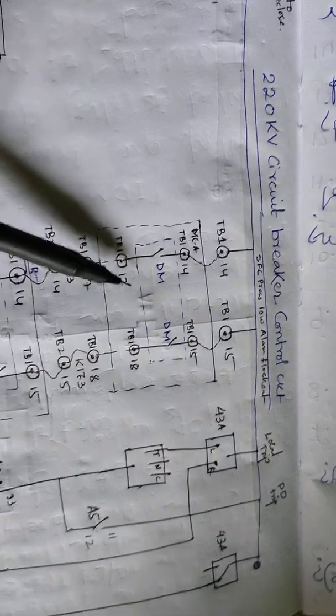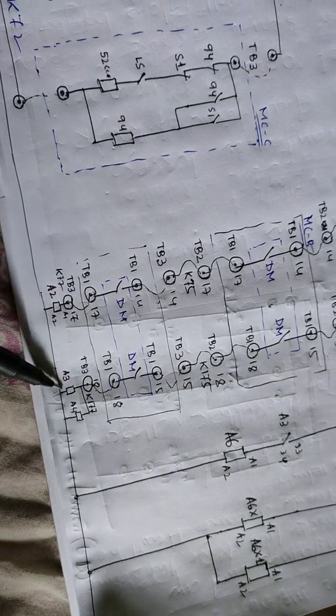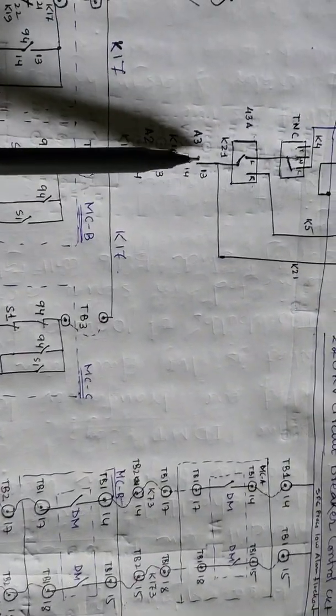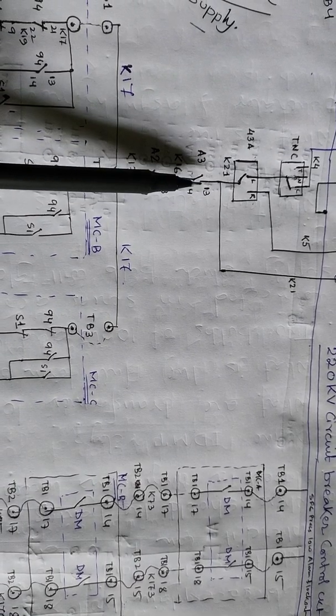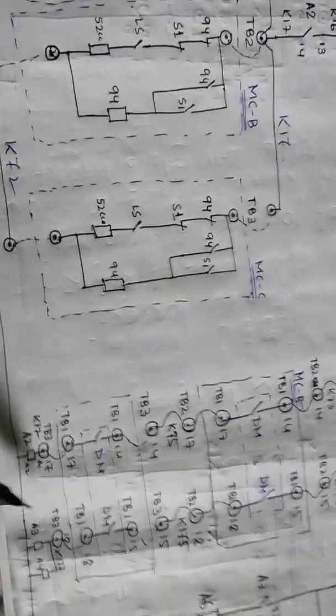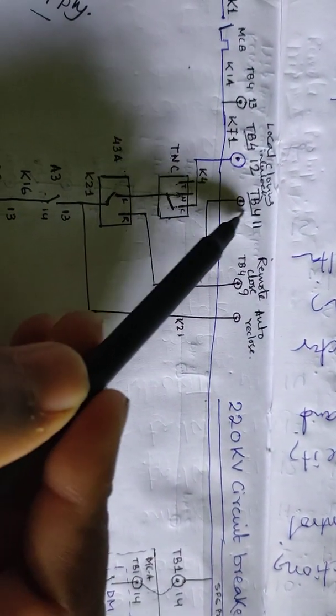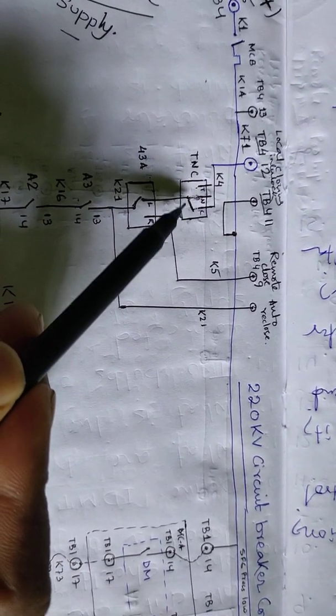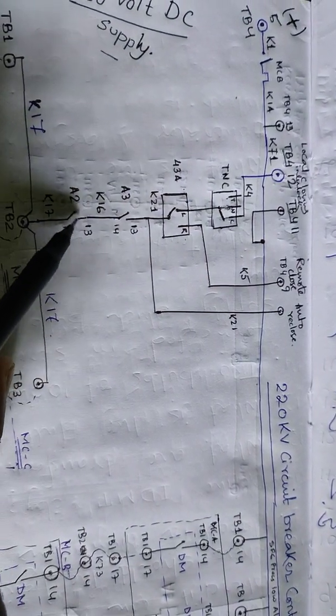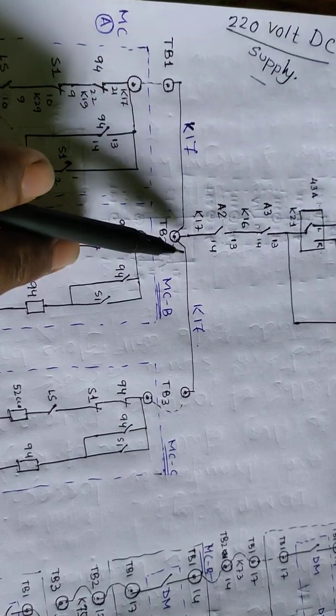If the SF6 gas pressure is in normal condition and the breaker is not locked out, then this terminal is normally closed - not normally open, normally closed. So all the contacts are closed and this coil is energized. If this A3 coil is energized, this NC contact will convert, and the A2 contact is a similar case - A2 contact is NC here. So the power from the DC supply goes through, giving a close pulse.